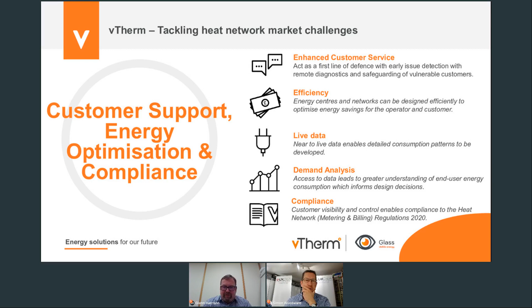I said earlier that the ability to understand the heat network and have an optimized heat interface unit working at lower temperature gives maximum benefit. Where you've got a low temperature heat network and an HIU optimized to work at those lower temperatures, you get real benefit.